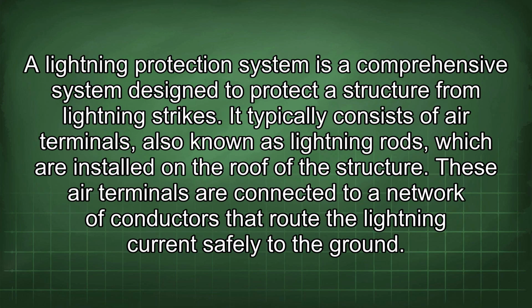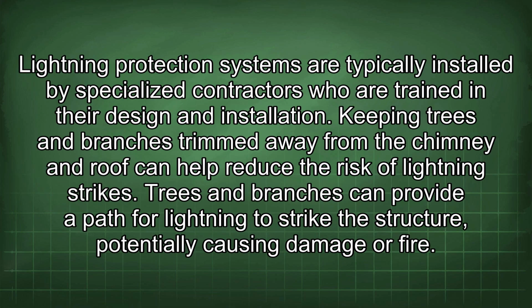A lightning protection system is a comprehensive system designed to protect a structure from lightning strikes. It typically consists of air terminals, also known as lightning rods, which are installed on the roof of the structure. These air terminals are connected to a network of conductors that route the lightning current safely to the ground. Lightning protection systems are typically installed by specialized contractors who are trained in their design and installation.